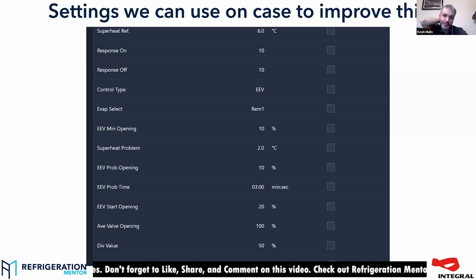As you touched on, control type EEV is superheat related. So, evaporator select on this, REM 1, means that it's sourcing the evaporator pressure from a remote source, be that the network or from the local hub it's connected to, rather than a local transducer. So as you can see on this, my problem opening and my minimum opening for the EEV are quite low. They're not zero, but they're quite low. And the superheat problem is 2 degrees. That's to make sure that the valve does shut down a bit if the superheat gets too low on it. You can, depending on how stable your coil is, tweak those numbers around.